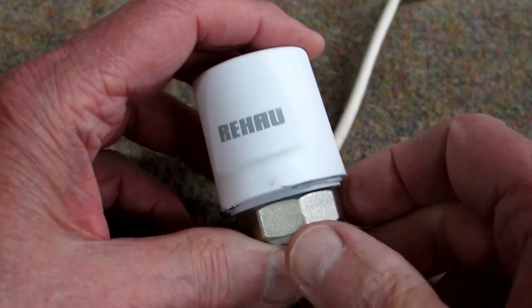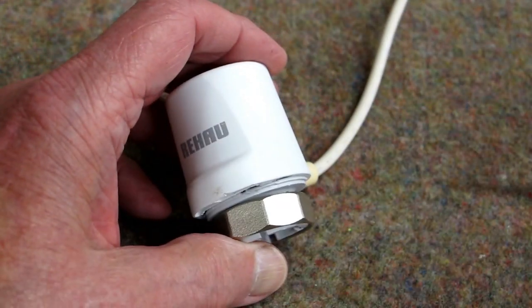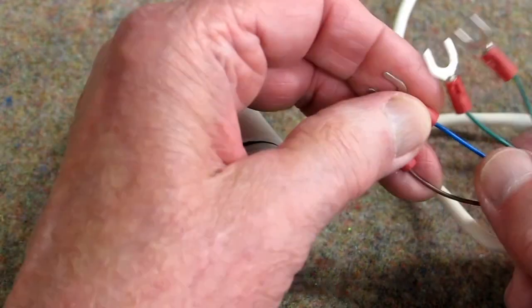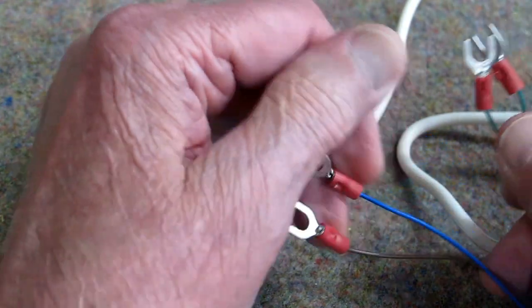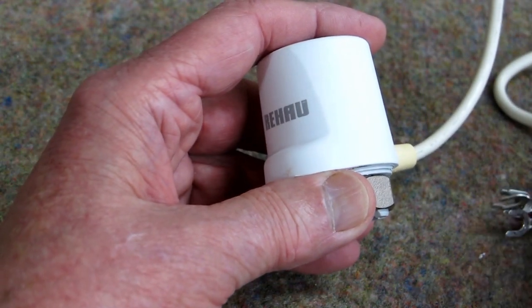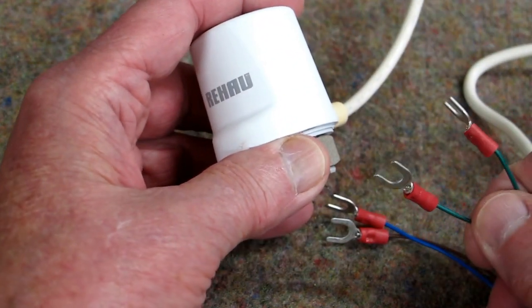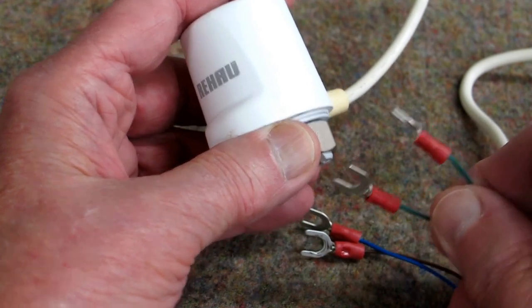This is a Rehau 4-wire actuator, also called a wax motor. It has four wires. You put 24 volts AC across these two, and these are supposed to be an end switch. When this starts to get close to the open position, or has reached the open position, it's supposed to close a set of contacts. The wax motor part of this worked; the end switch did not.